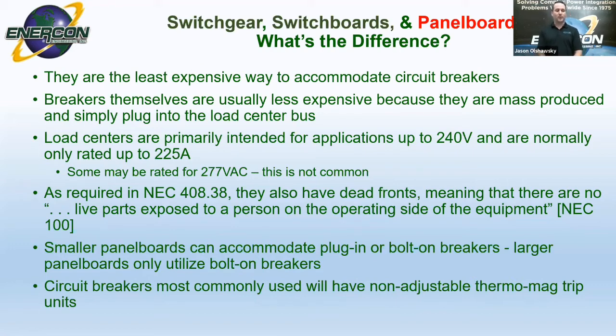So smaller panel boards can accommodate plug-in or bolt-on breakers. Larger panel boards only utilize the bolt-on style breakers as they're going to carry more physical weight, and the bolt-on just helps to keep those in place. Circuit breakers most commonly used will have non-adjustable thermal mag trip units, as we discussed before. That really limits your ability to change time and set points, but you'll still have that same overcurrent and short circuit protection.